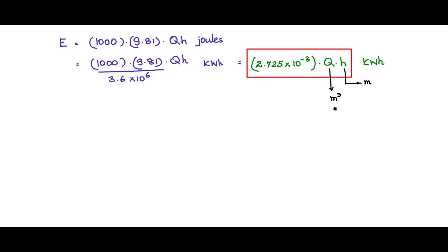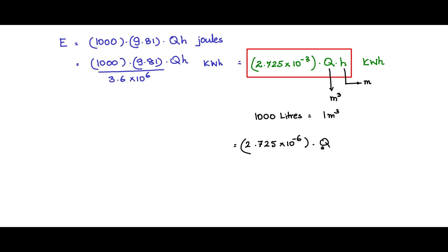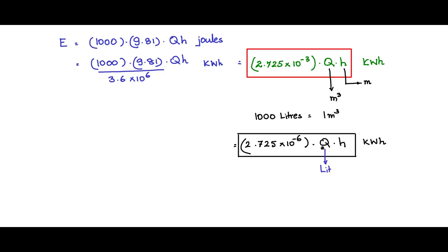In this expression q is in cubic meters. However, a much more common and intuitive unit for q is liters, and it is much easier to imagine in liters than in cubic meters. The relationship is 1000 liters equals 1 cubic meter. Therefore, if you want to express the equation with q in liters, replace 10⁻³ with 10⁻⁶ — essentially dividing q by 1000 — giving 2.725×10⁻⁶ × q × h kilowatt-hours, where q is in liters.